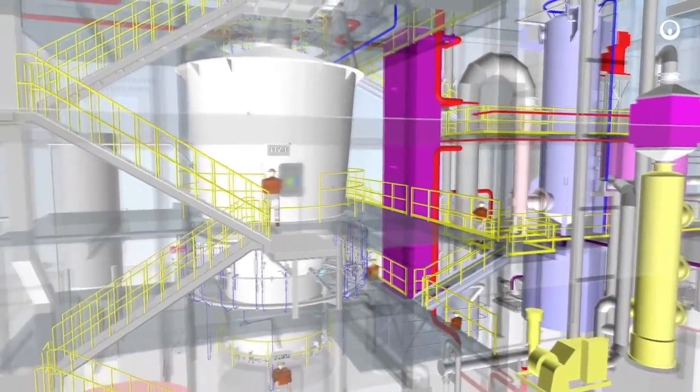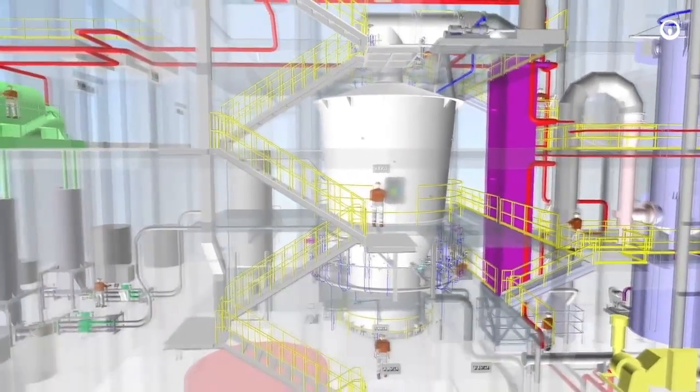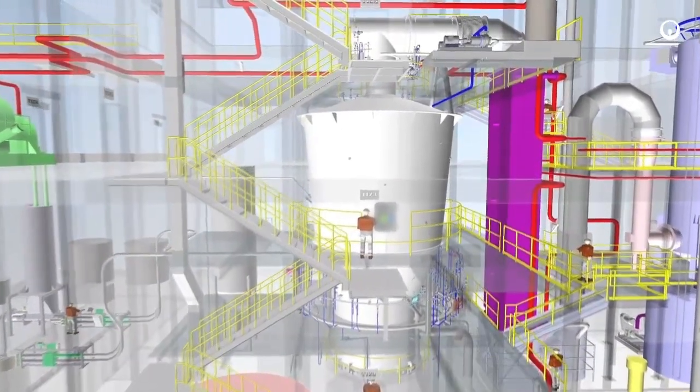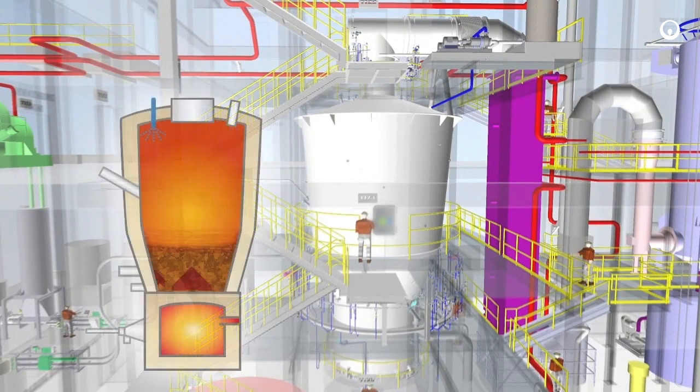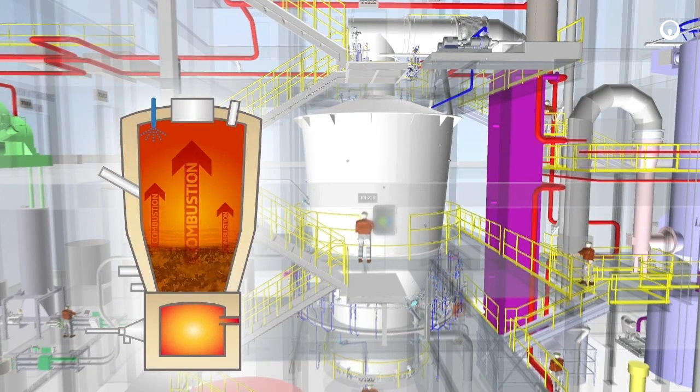The teardrop shape expanded freeboard design with 2.1 feet per second gas velocity allows the hot gas velocity to further decrease, eliminating sand loss from entrainment.